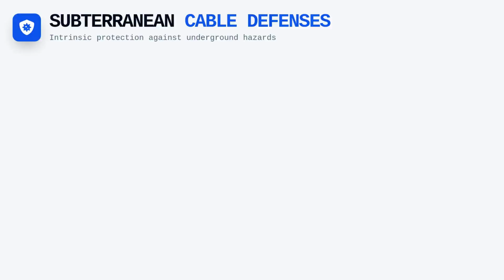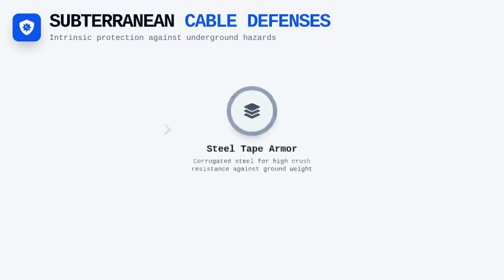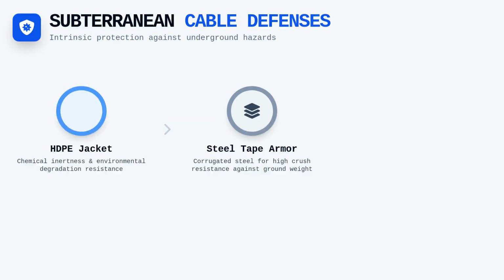The cables themselves must possess intrinsic defenses against these subterranean hazards, leading us to utilize specific material configurations like corrugated steel tape armor. This metallic layer provides high crush resistance, which is essential when the weight of the overhead ground is factored into the long-term strain on the cable. Beyond the metal armor, heavy-duty, high-density polyethylene jackets are standard because of their chemical inertness and resistance to environmental degradation.